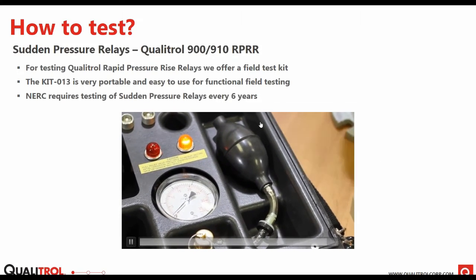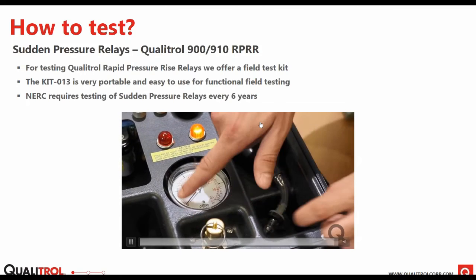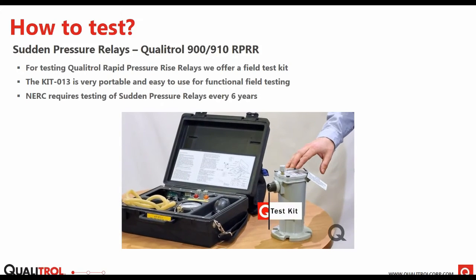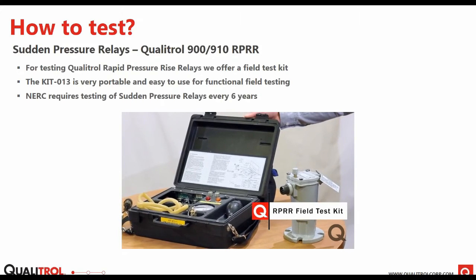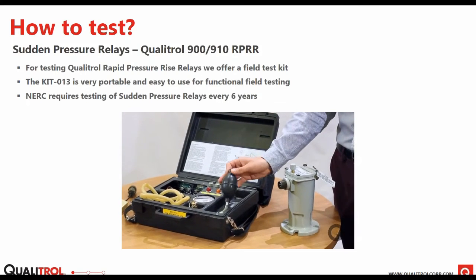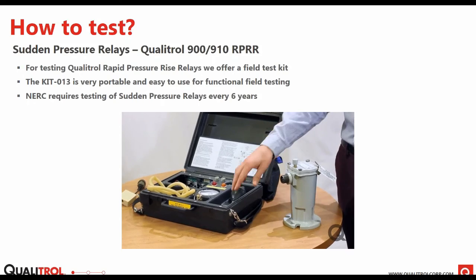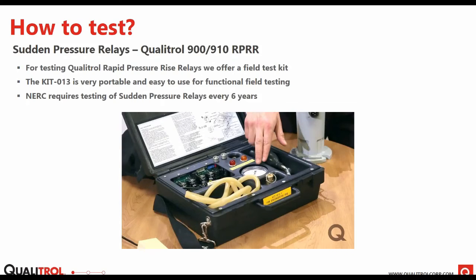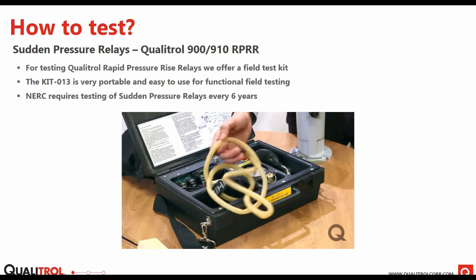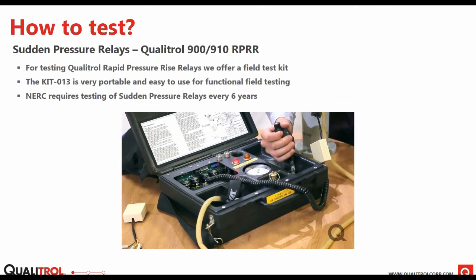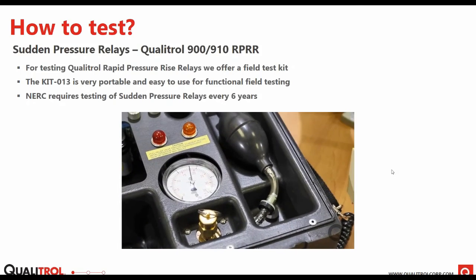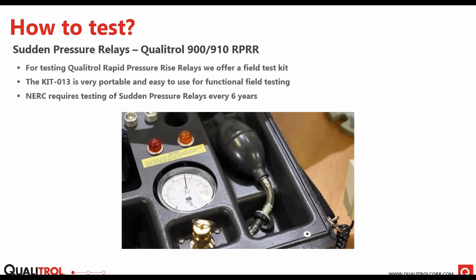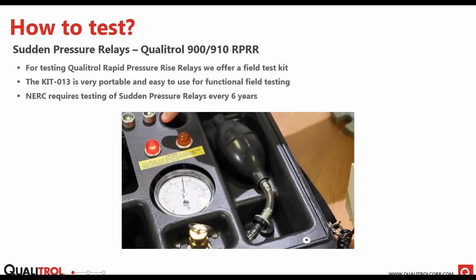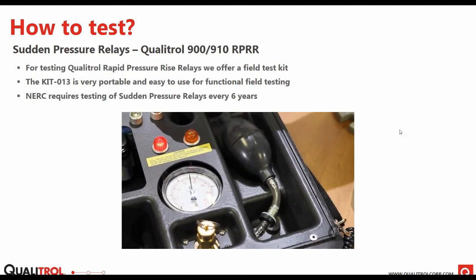Just to reiterate, you're applying pressure on top of the bellows system, waiting for that to level out, and then you're relieving that pressure quickly on top, which simulates a sudden pressure on the bottom, or in the tank. This can all be done with our field test kit. And with increasing regulations, there's actually a NERC requirement that requires the testing of mechanical sudden pressure relays every 6 years, which this falls into that category. Our field test kit makes it really easy to do so.